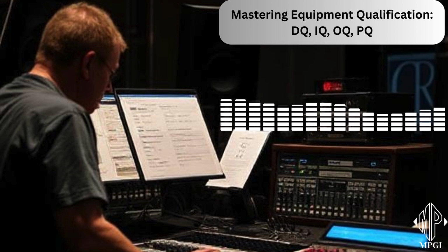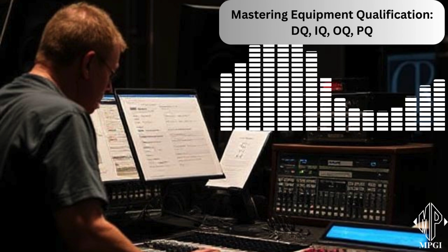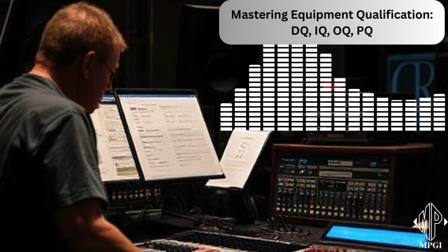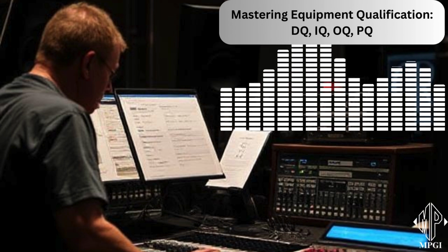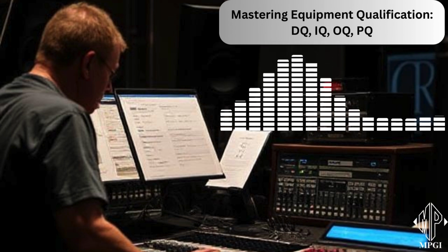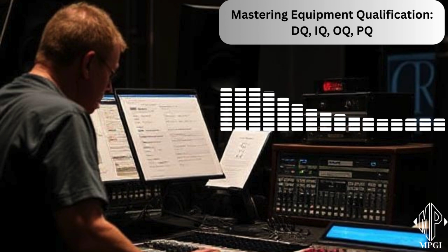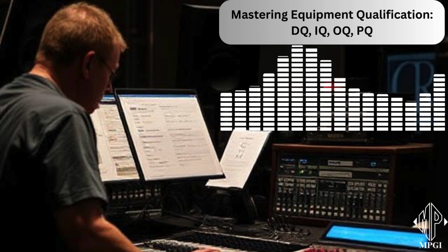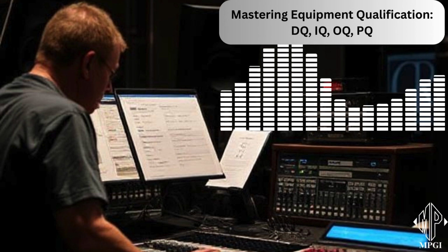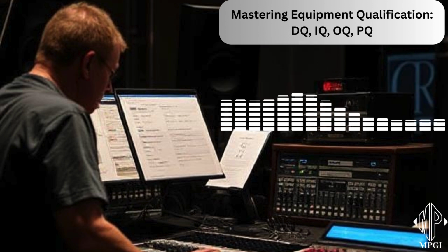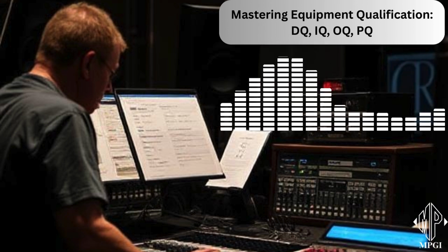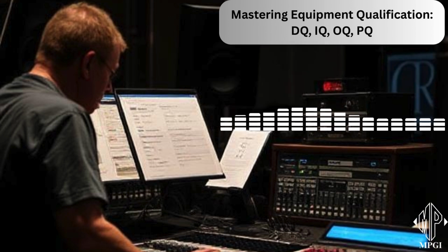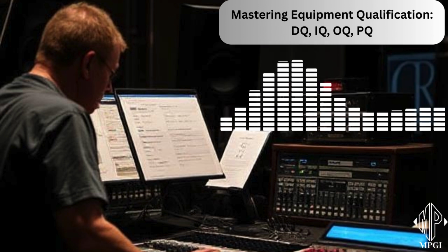So the design's good, it's been installed properly, now it's time to see if it actually works, right? That brings us to operational qualification, or OQ. Right. Now we're going to see if this thing actually does what it's supposed to do. We're making sure the equipment operates correctly within the manufacturer specs and the user requirements we discussed earlier. So IQ is about putting it together right. OQ is about making sure it runs right. Exactly. OQ is all about testing and documenting that the equipment performs as intended. We need proof that it functions properly.